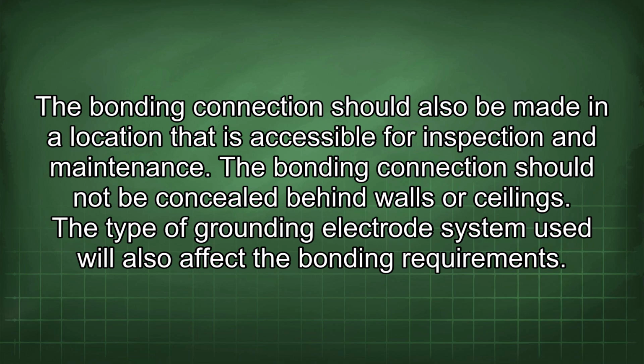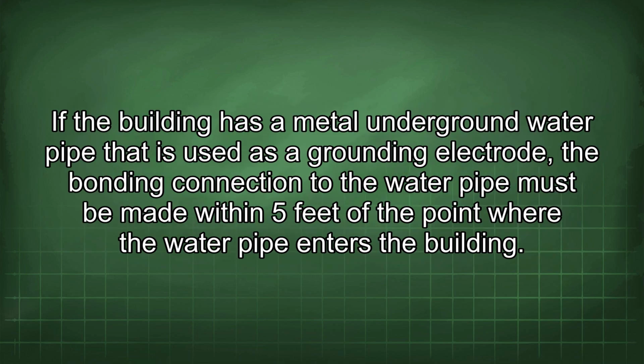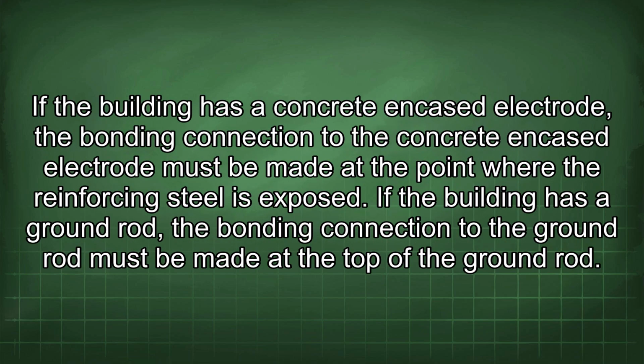The type of grounding electrode system used will also affect the bonding requirements. If the building has a metal underground water pipe that is used as a grounding electrode, the bonding connection to the water pipe must be made within 5 feet of the point where the water pipe enters the building. If the building has a concrete encased electrode, the bonding connection to the concrete encased electrode must be made at the point where the reinforcing steel is exposed. If the building has a ground rod, the bonding connection to the ground rod must be made at the top of the ground rod.